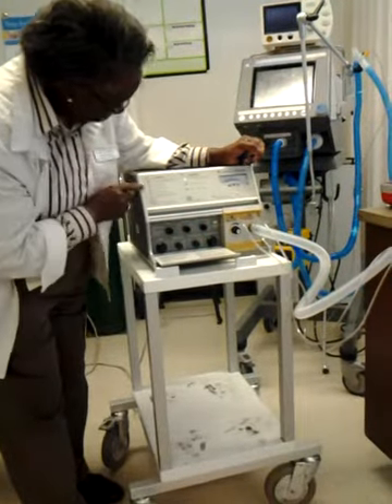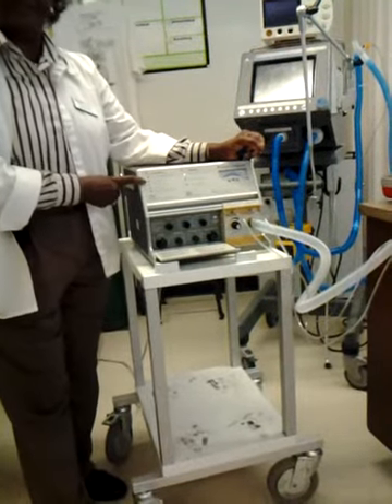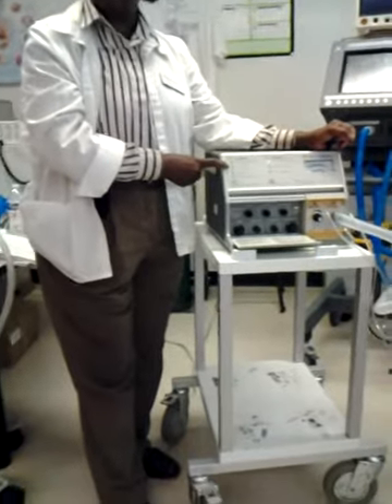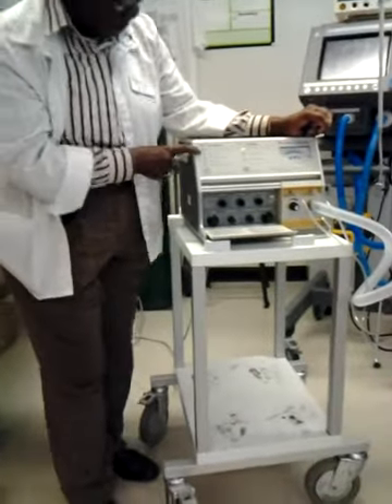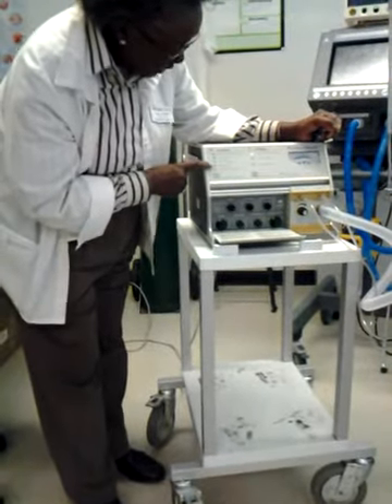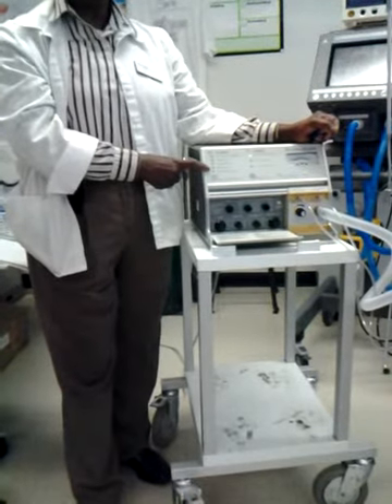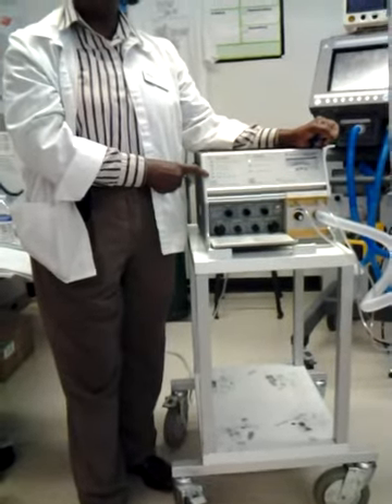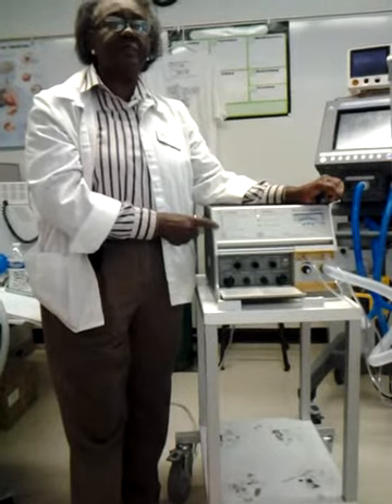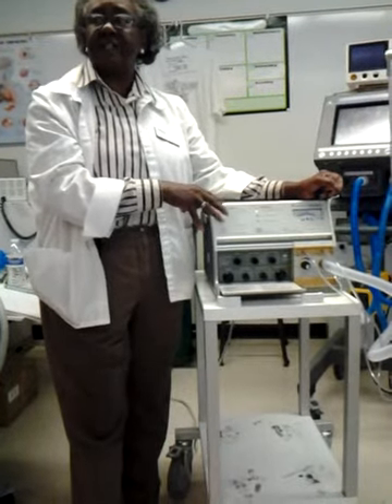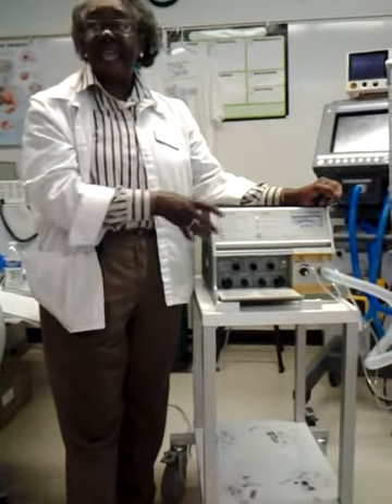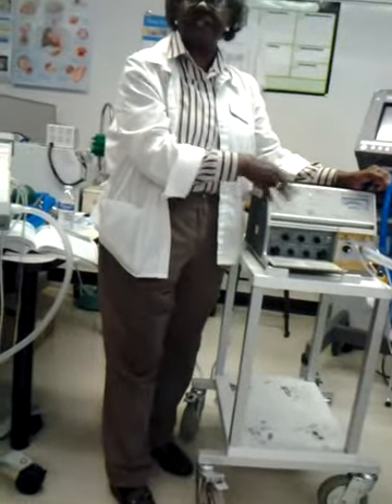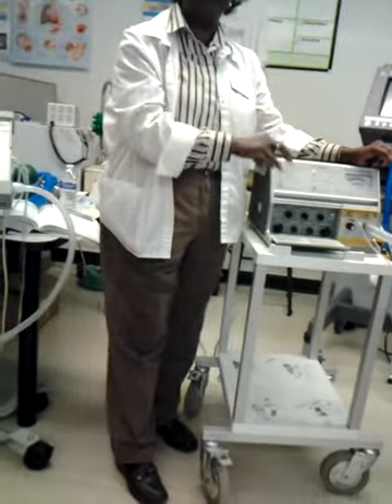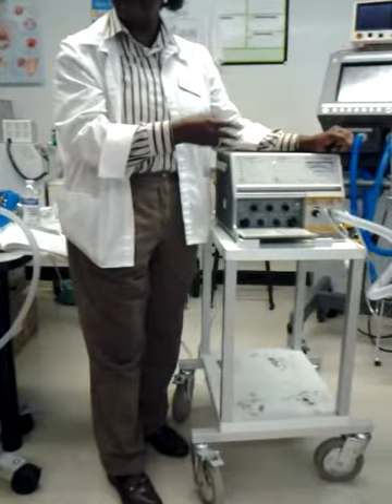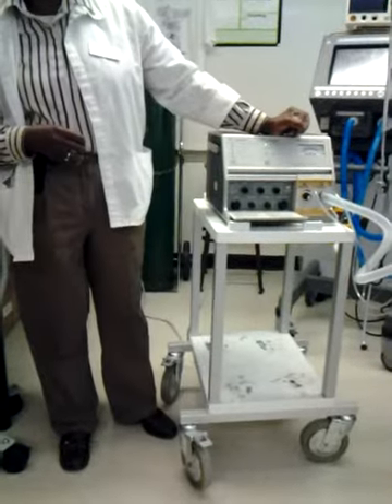I have a low power alarm: if the battery goes out or if the electricity goes out, you're going to get the low power alarm. High pressure. Setting error. This is not an alarm that you set. If you set something on the ventilator that's not compatible, you will get the setting error alarm. So the machine will let you know that something here is not right. Your I time is too long or too short, or your rate or something. What's setting error? Yeah, it's right here, setting error.